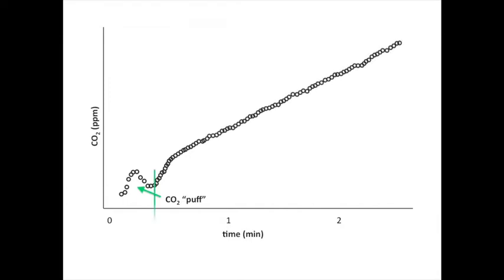The closing of the chamber at the beginning of the measurement can also cause pressure changes. When the chamber comes down, it usually causes a puff of CO2 to leave the soil. Since the measurement begins as soon as the chamber closes, we must adjust our estimate of CO2 efflux, making sure we account for the initial disturbance caused by the chamber closing. We call this the dead band, and it is usually set to 20 seconds. When we calculate our CO2 efflux rate, we use the data from the end of the dead band to the end of our measurement period.